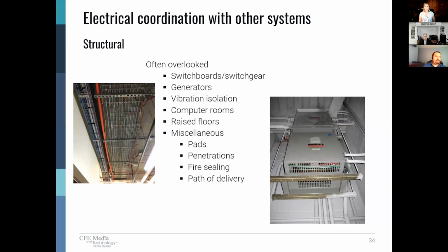Penetrations, especially where you've got very tight floor to floor on projects and structural members that are supporting the upper decks appear to be in your way. I mean, trying to make a path for your conduits or for cable tray, etc. Those penetrations need to be carefully coordinated with the structural engineer on the project to make sure that we're not penetrating and causing an issue with the integrity of the structural system. Of course, fire sealing, and then the path of delivery, where you've got multiple conduits, a conduit bank running through a building that's suspended, for example. These things add significant weight per linear foot, and it's important that we have that fully coordinated with the structural engineer on the project.